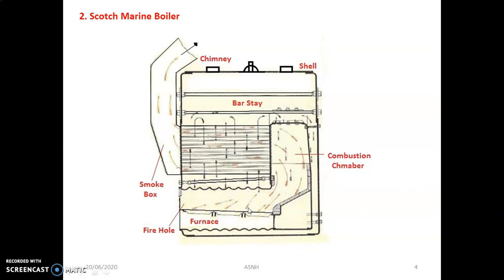After combustion, whatever burnt gases are produced travel through the tubes and are collected in the smoke box, from which the smoke finally exits through the chimney. This is a cylindrical type boiler mostly used for medium capacity applications where the pressure requirement is approximately 17 to 20 bar. In the fire tube boiler, fire continuously passes through the tubes and the remaining portion is surrounded by water.